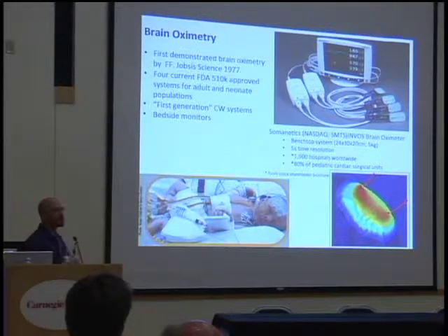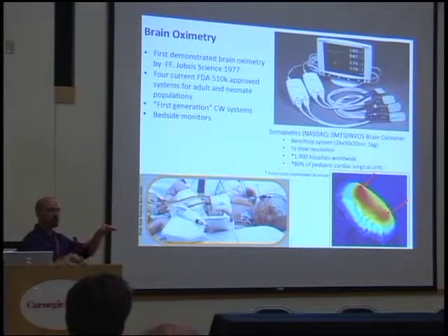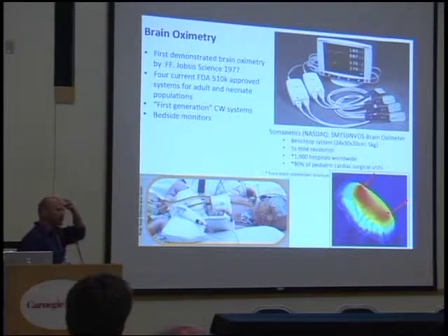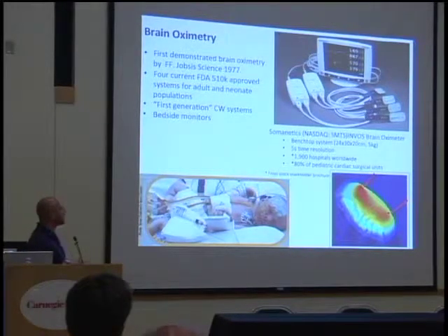And basically what it's doing is it's sending light in. That light is going into the tissue, it's diffusing through the tissue, and then you have a detector that's measuring what light came back out. By increasing the distance between that source and detector pair, the light is on average traveling deeper and deeper. And so you can find an optimal distance which gives you sensitivity to the brain. You can see on the baby's forehead, it's almost like a Band-Aid. Inside of that Band-Aid has a source and a detector mounted in it, and it's measuring the brain pulse oximetry.